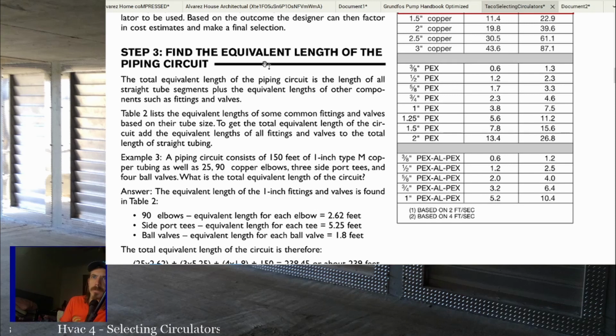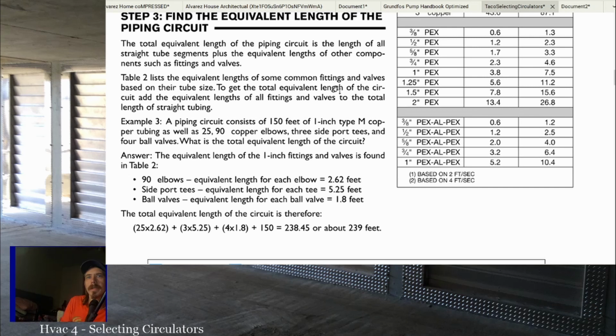So we've got to figure out how far we're going to run the piping circuit, how many T's are going to be in there, and all that. So you have to have a sketch of how you want to run the piping, or at least a good idea of how it's going to be run. And then you've got to find the equivalent length. Table 2 lists the equivalent lengths of common fittings based on their size. To get the total equivalent length of the circuit, add the equivalent lengths of all the fittings and valves to the total length of straight tubing.